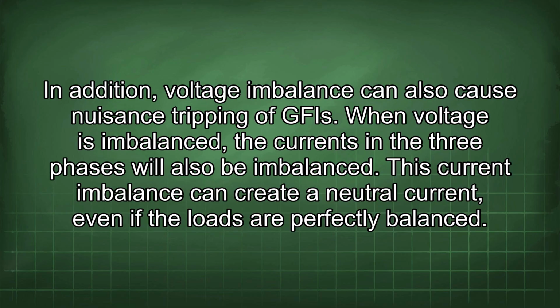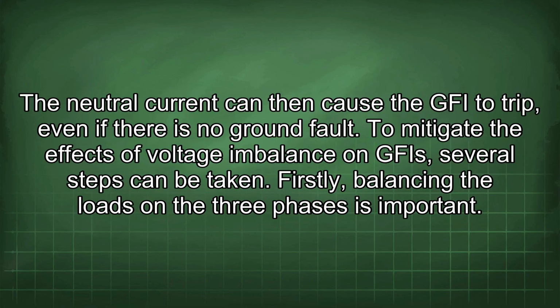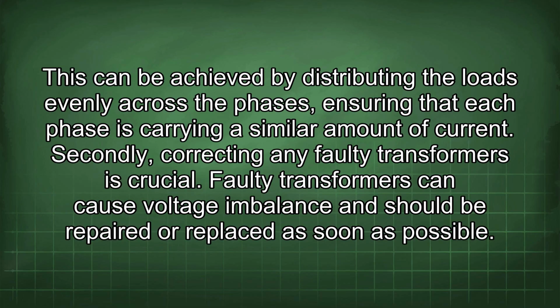When voltage is imbalanced, the currents in the three phases will also be imbalanced. This current imbalance can create a neutral current, even if the loads are perfectly balanced. The neutral current can then cause the GFI to trip, even if there is no ground fault. To mitigate the effects of voltage imbalance on GFI, several steps can be taken. Firstly, balancing the loads on the three phases is important. This can be achieved by distributing the loads evenly across the phases, ensuring that each phase is carrying a similar amount of current. Secondly, correcting any faulty transformers is crucial.